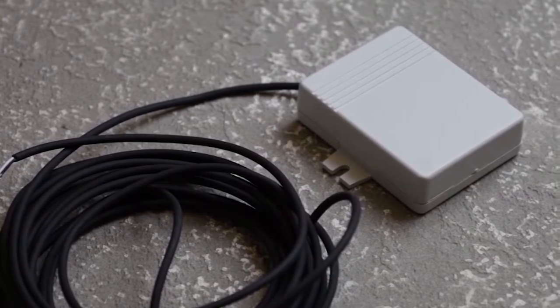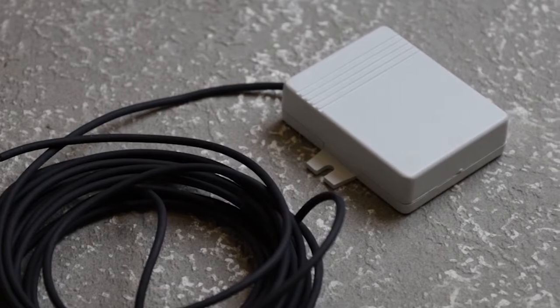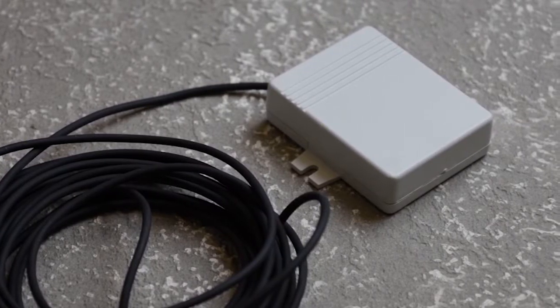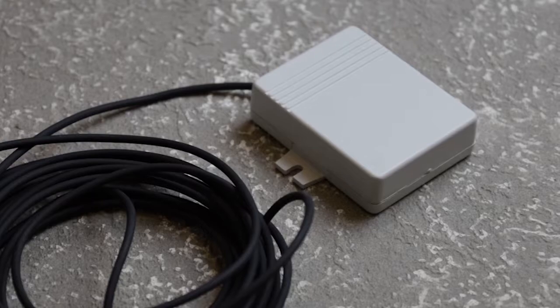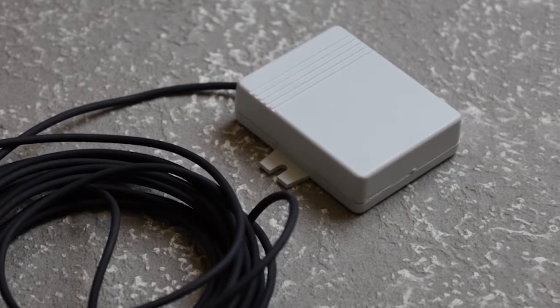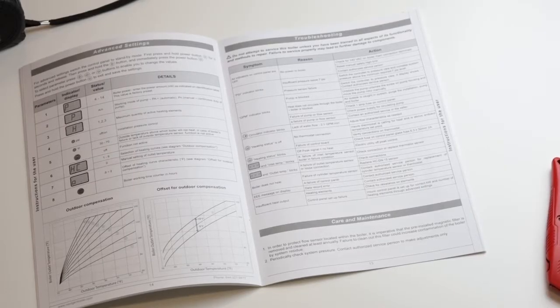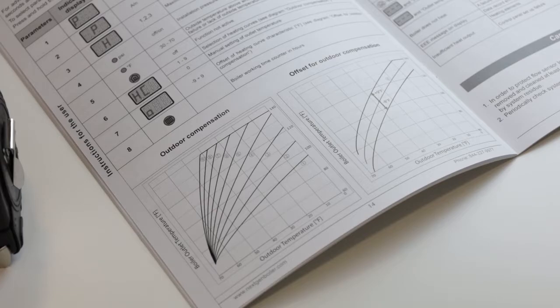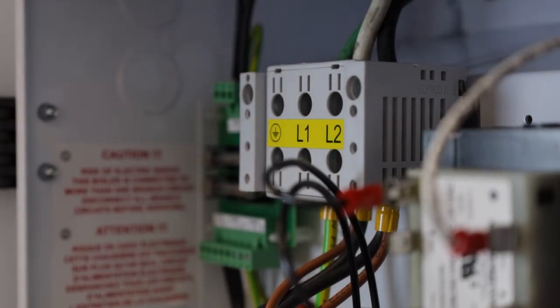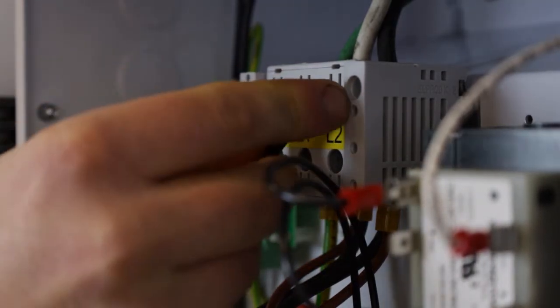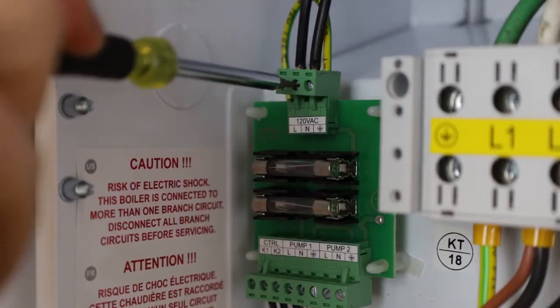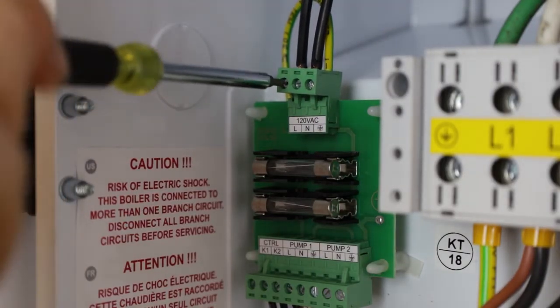The last part of the electrical installation on the boiler is the option to use the outdoor sensor. This is used for outdoor compensation capability. Our recommendation is to install the sensor on the north side of the building. The sensor should be kept away from any heat source. Refer to the advanced setting selection of the manual to properly set the heat curve. As a final check, verify all electrical connections are tight. Loose connections can cause premature failure of the electrical components.